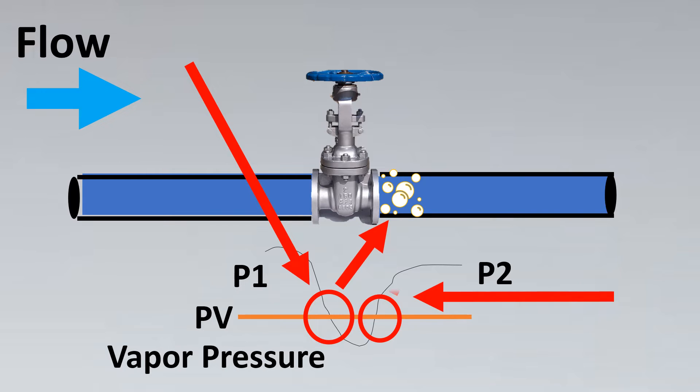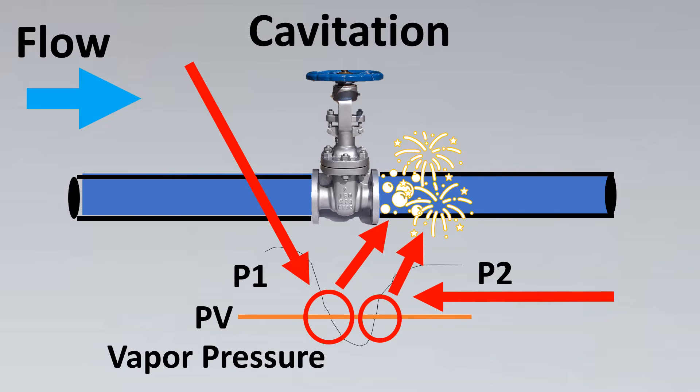At the exact opposite side, if you notice, the vapor is going to turn back into liquid state. Here what is going to happen is the bubbles are going to burst to come back to liquid state, which is called popping, which has very high velocities that can damage the valve and the piping downstream. This entire phenomenon is called cavitation.